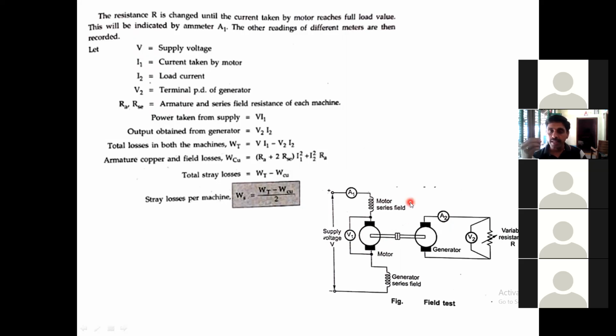Suppose the motor's full load current is 19 amperes. Until 19 or 18 amperes is reached, you have to vary this resistance, so that the current taken by the motor reaches the full load value. It will be indicated by A1. What is the current taken by the motor indicated by A1?